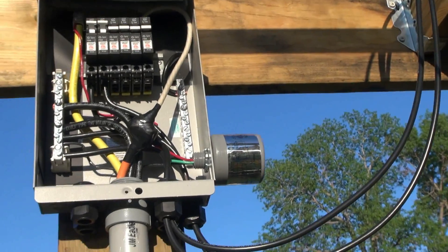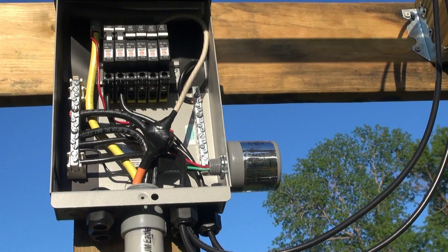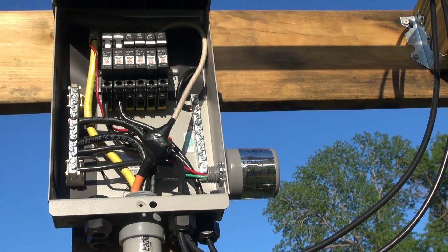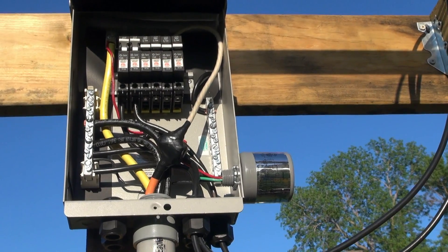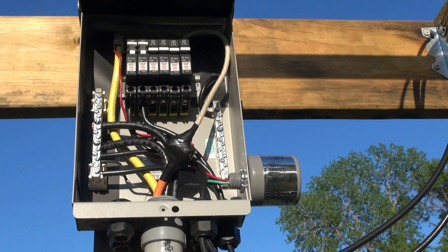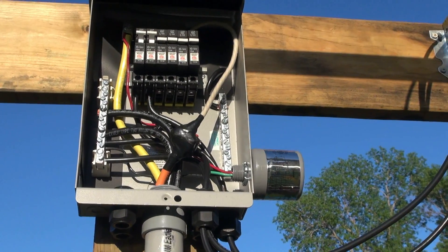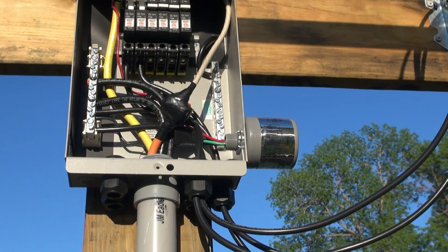The question I did have is on that lightning arrester — you can see the red wire goes up to the main bus bar, and then the green goes to the neutral ground — I meant the earth ground — and then the black goes to the negative. And on that same bus bar there's a big black wire. I drilled a hole in the back of that Midnight Solar and I'll put some RTV there. I don't even know if that lightning arrester is wired right. It's kind of weird how that's done — you're going to have to let me know.